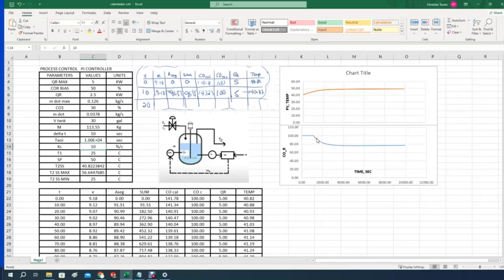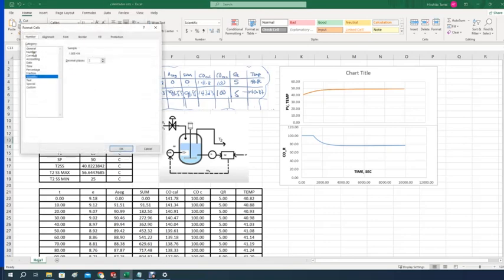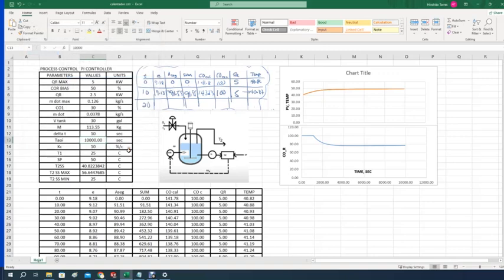And on the other hand, the oscillation on the controller was very small. From 100, it dropped to a little bit less than 80 and stayed pretty much there. Now, how about if I drop this tau I? Let me change the format, because I don't like it. Let's put numbers and say okay. Now, instead of 10,000, how about if I drop it to 5,000?